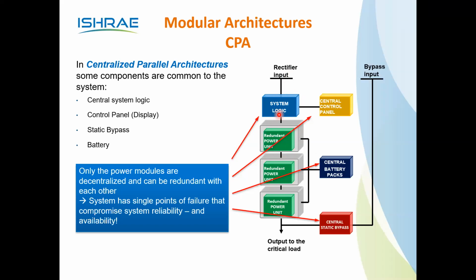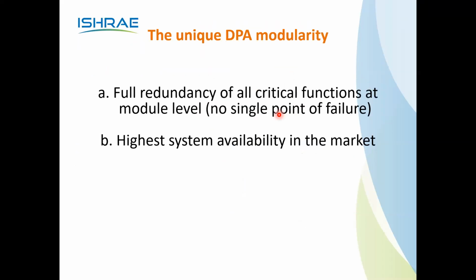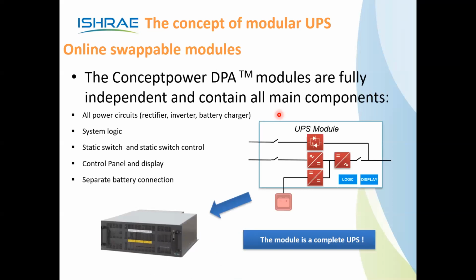Okay, master-slave configuration. What is the right technology in modular? Full redundancy of all critical functions at module level. How is it going to be? Highest system availability in the market. This is the module. You can see this is a complete UPS module. Each UPS module has a rectifier, inverter, battery charger, system logic, static switch, control panel, separate battery connections, everything. It's a complete UPS module.